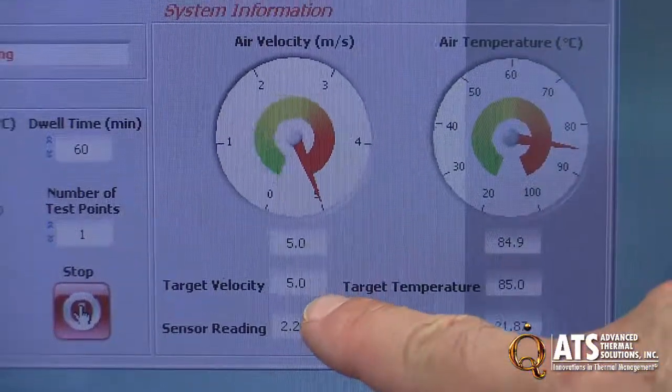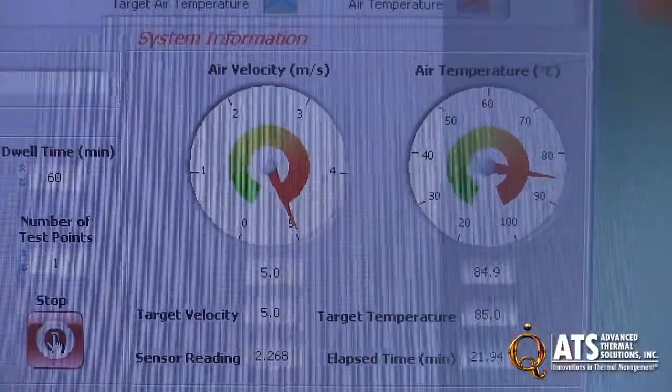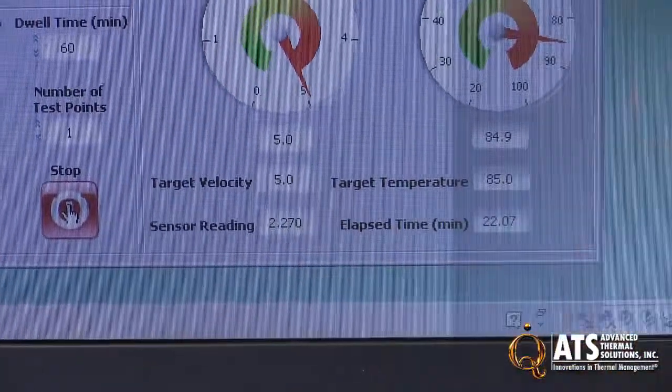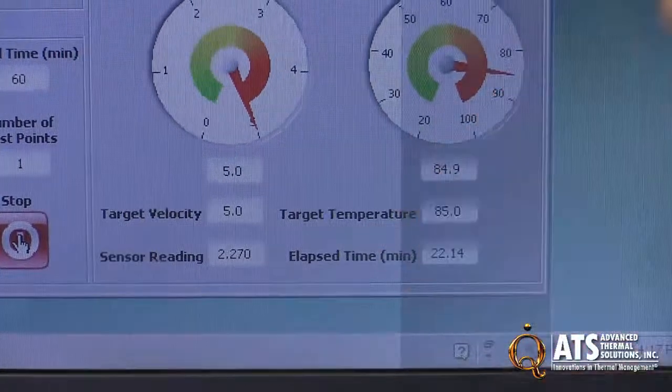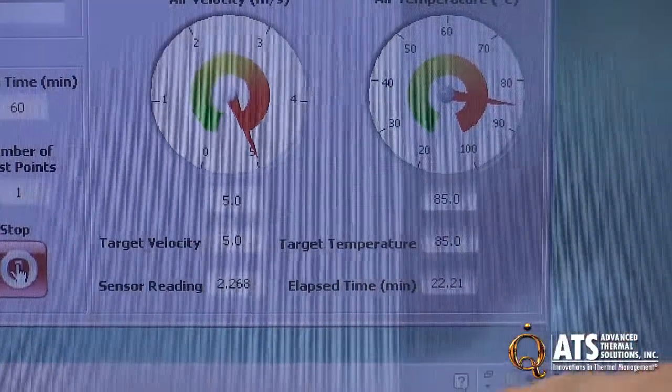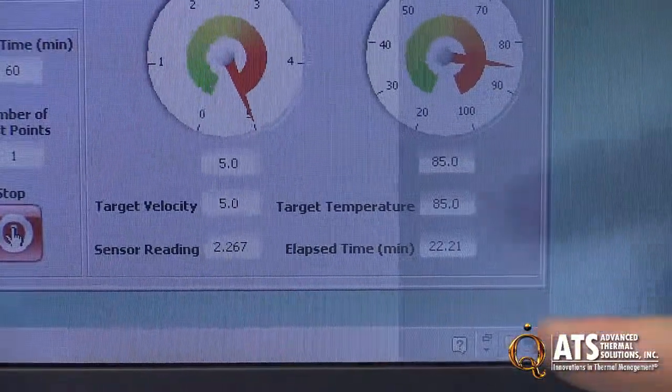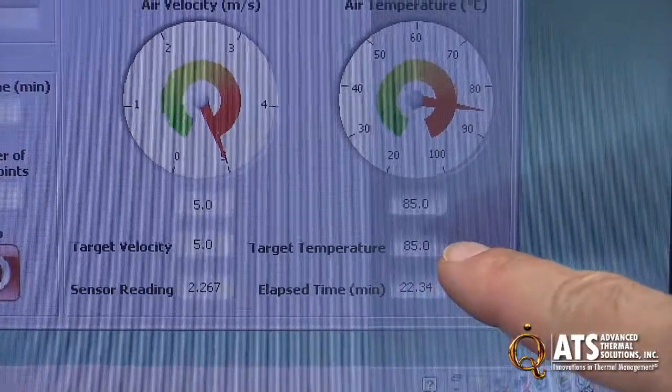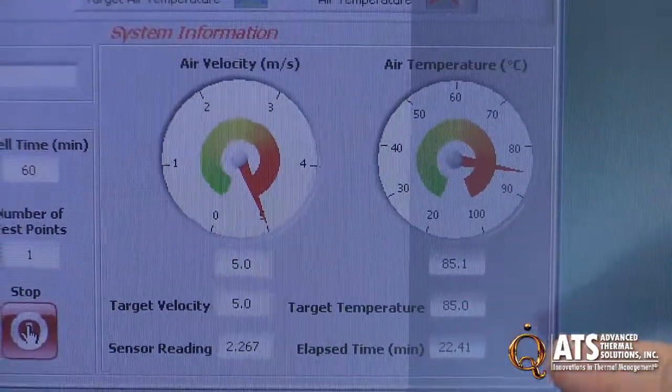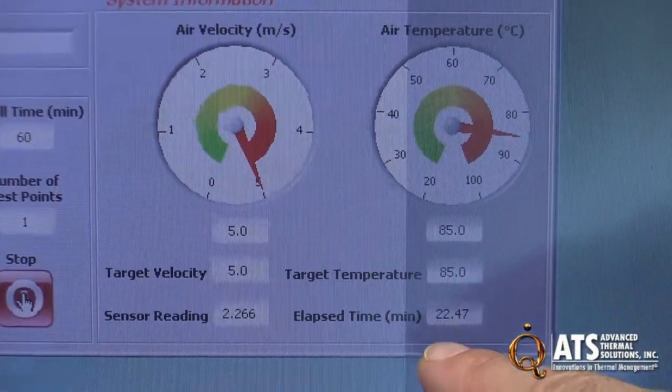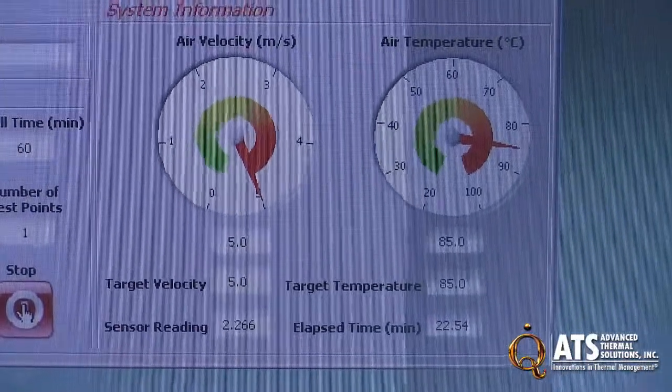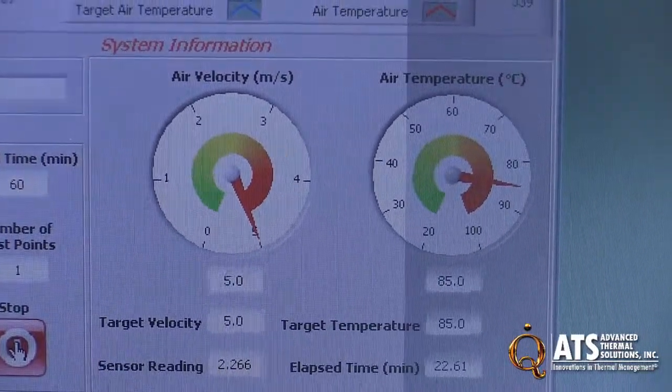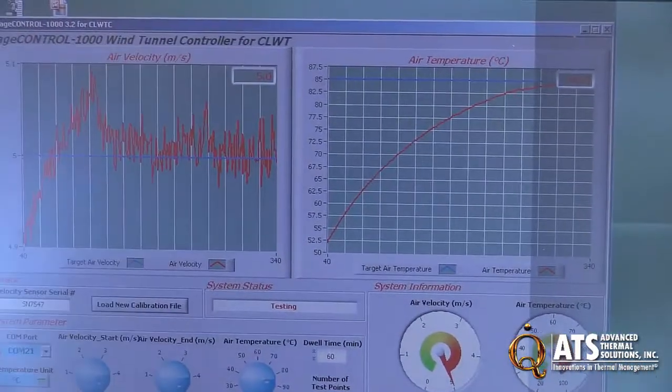That's the target velocity, which is 5 meters per second, and that's the velocity measuring now, which is 5 meters per second. This is the sensor reading in volts—2.268 volts—which the user doesn't really need; it's just for diagnostic purposes. We also have target temperature at 85 degrees C and instantaneous temperature the same at 85 degrees C. Elapsed time is 22 minutes out of 60 minutes. So within 20 minutes we have reached 85 degrees C at 5 meters per second.